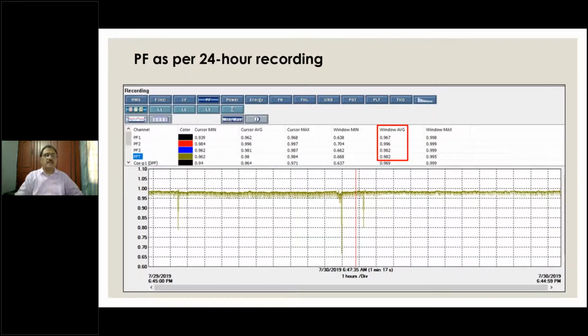So same hospital, same 24-hour recording, but different parameters. We are looking at the power factor. So you will have power factor in R, Y, B phase, and also the total. PFT is total, which is the sum of the three. So the average power factor is 0.982, but you will find that in the R phase, the power factor is 0.967. So we'll have to find out why in one phase the power factor is lower when compared to the other two phases.